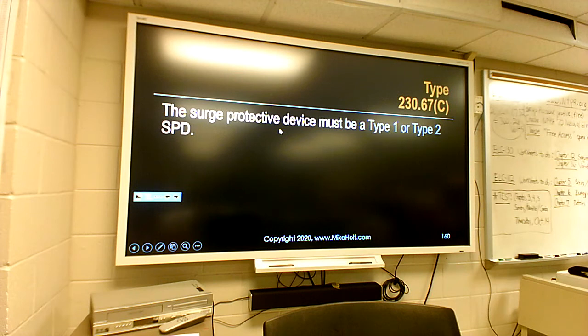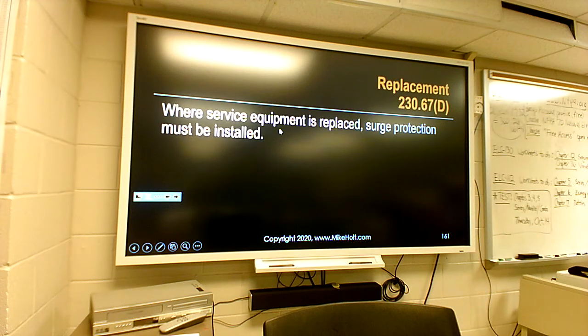Your surge protective device, abbreviated as SPD, must be a type 1 or type 2. Whenever you replace service equipment, you have to put surge protection in there now. It's actually 2020 code now. The new code says you've got to have it.